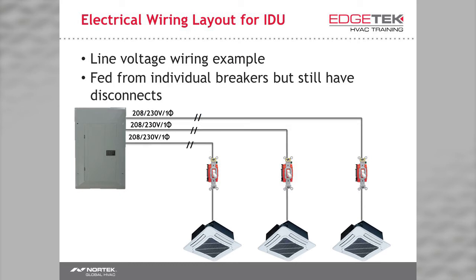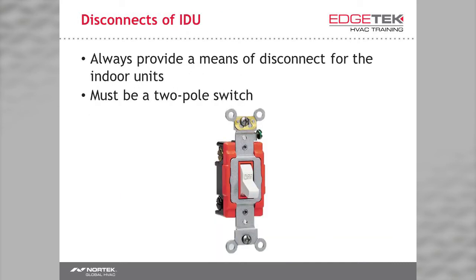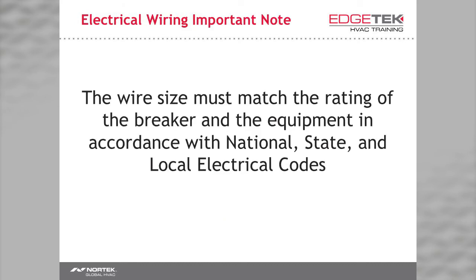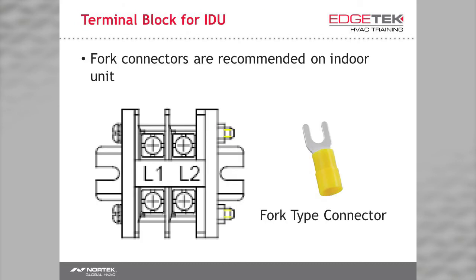Another example is providing a single breaker in the panel for each indoor unit while providing another current protection device within the disconnect serving that unit. You must have a way to safely de-energize your equipment. One way is to use a properly rated 2-pole switch. I invite you to read aloud with me. Your wire size must match the rating of the breaker and equipment in accordance with the national, state, and local electrical codes. For a great connection for your electrical wiring, I suggest using fork-type connectors.